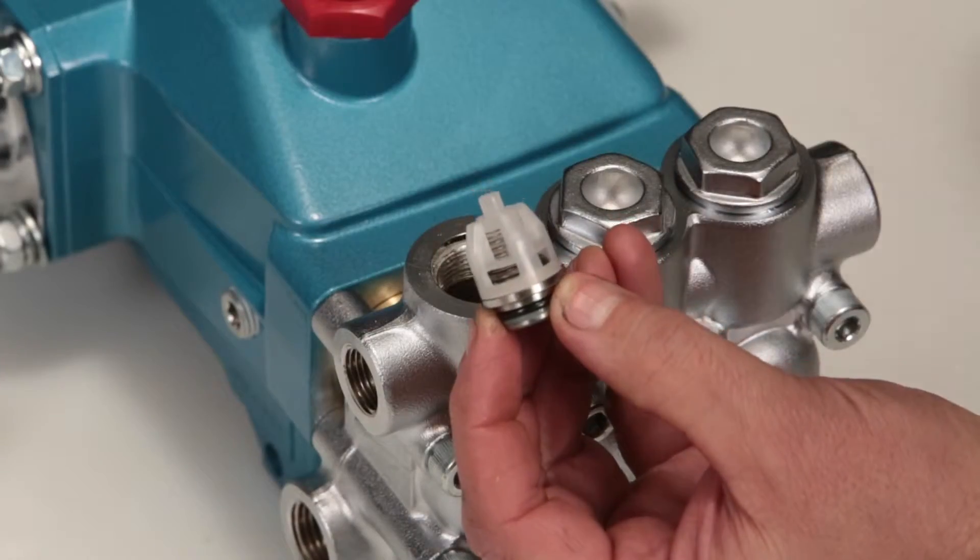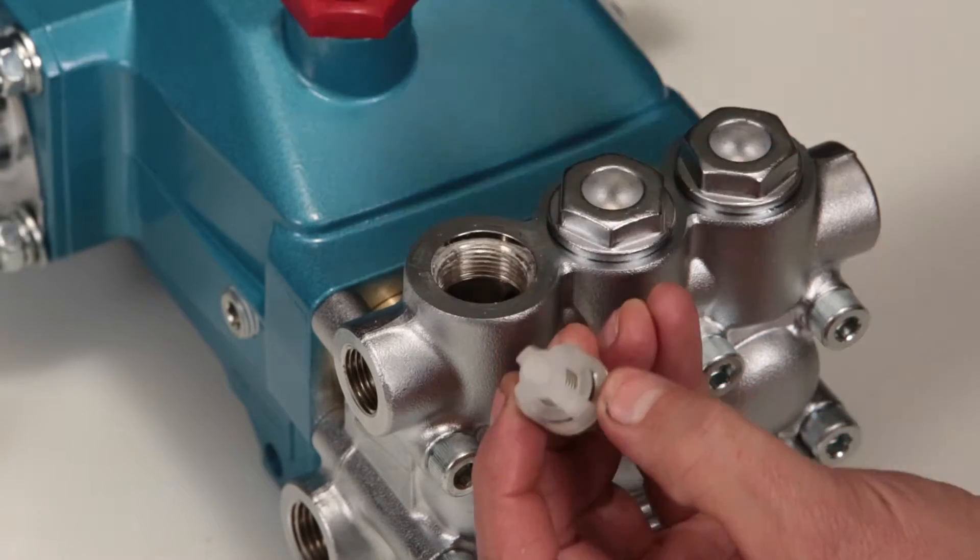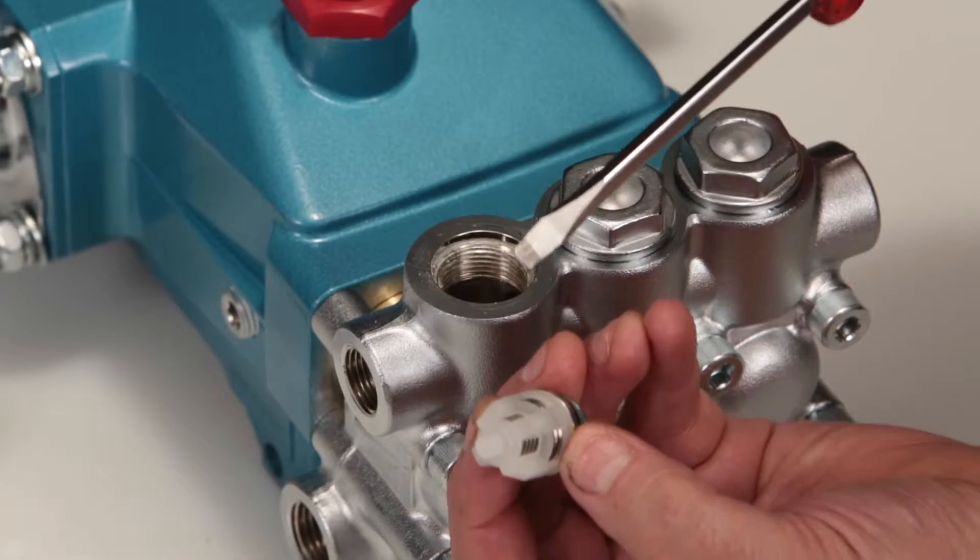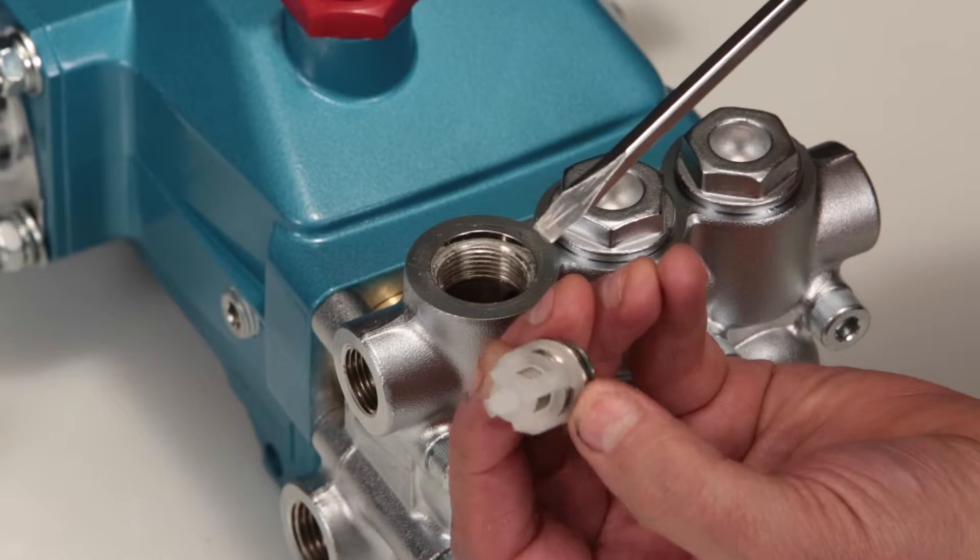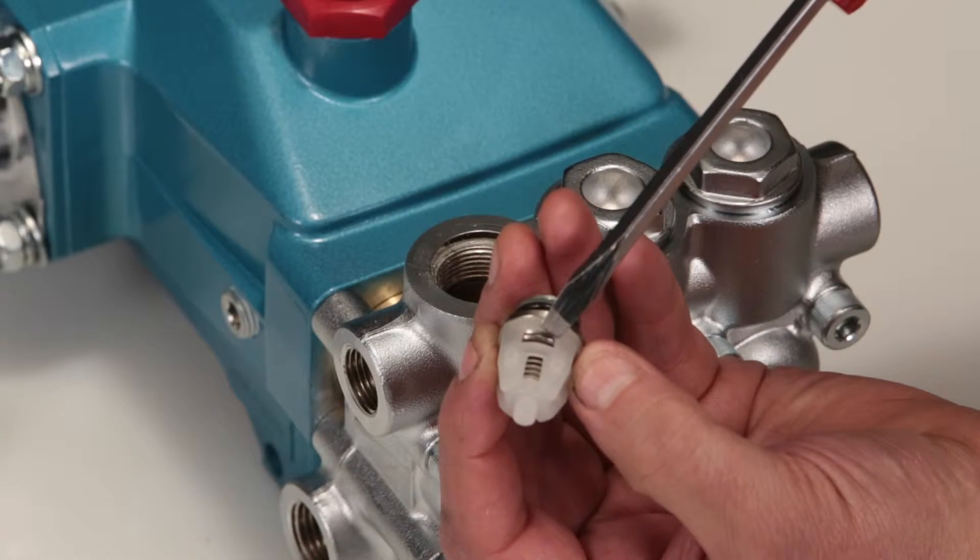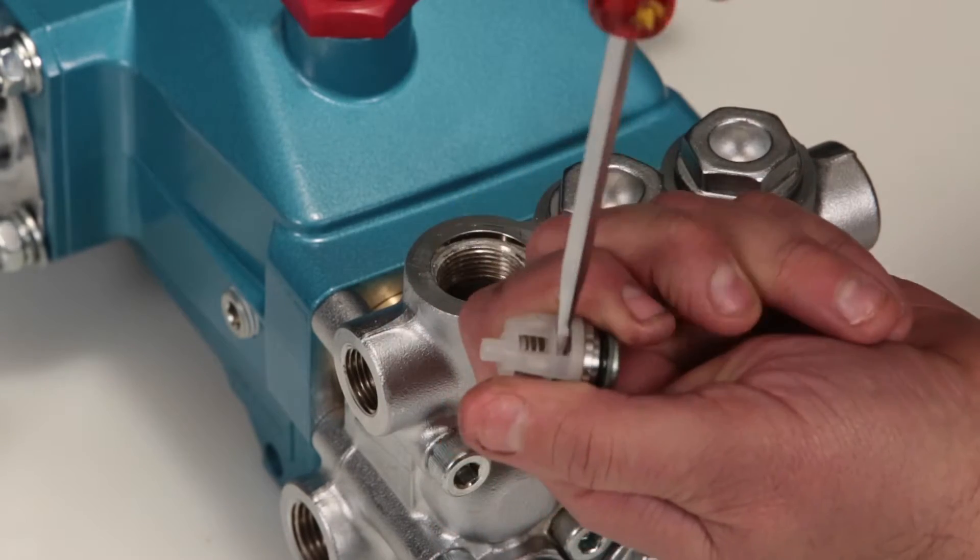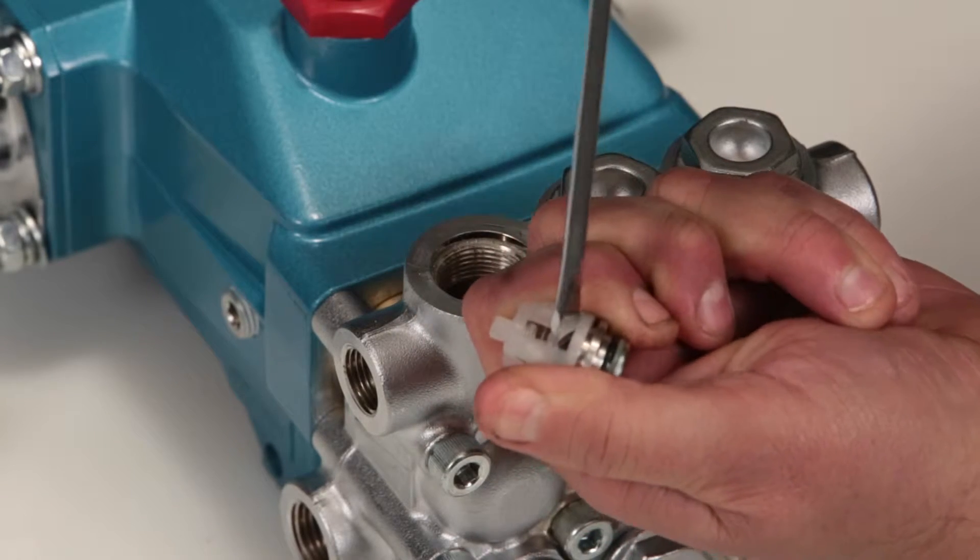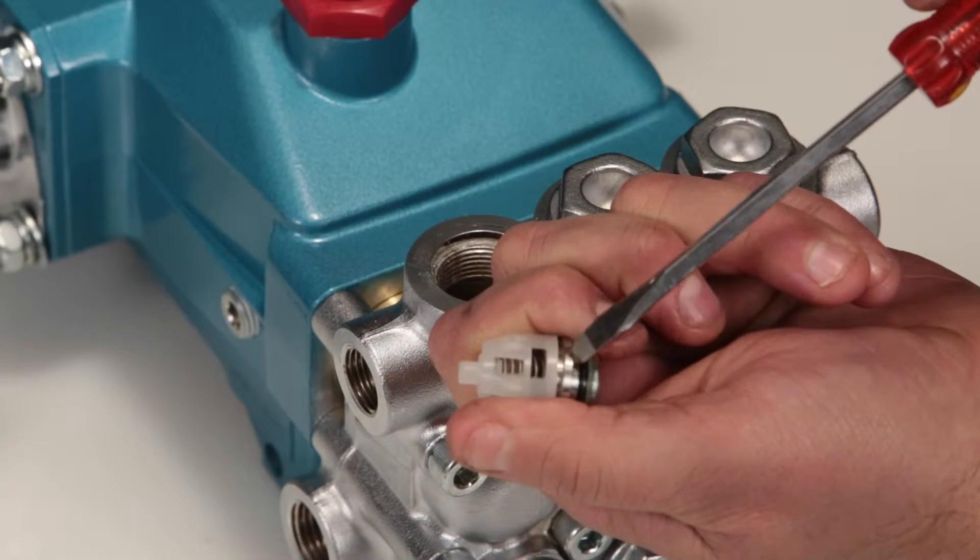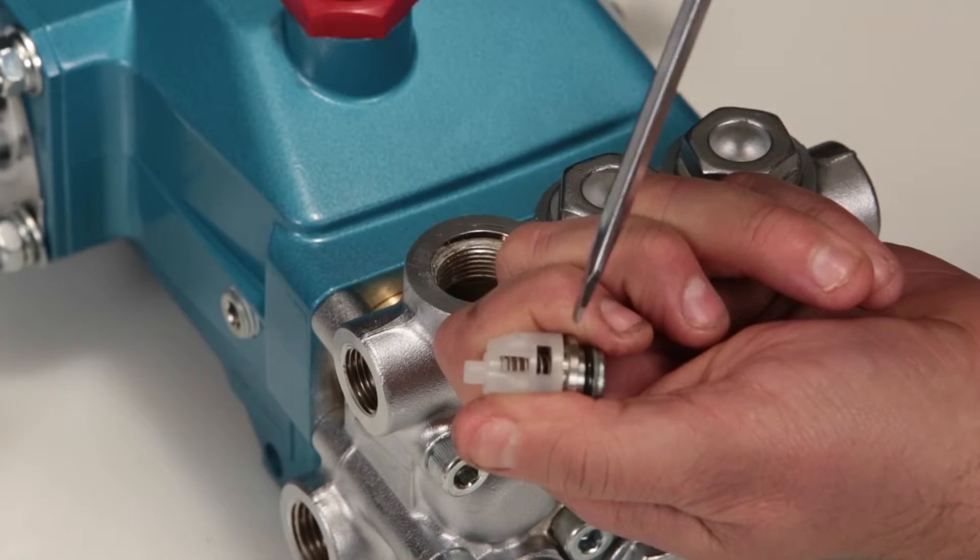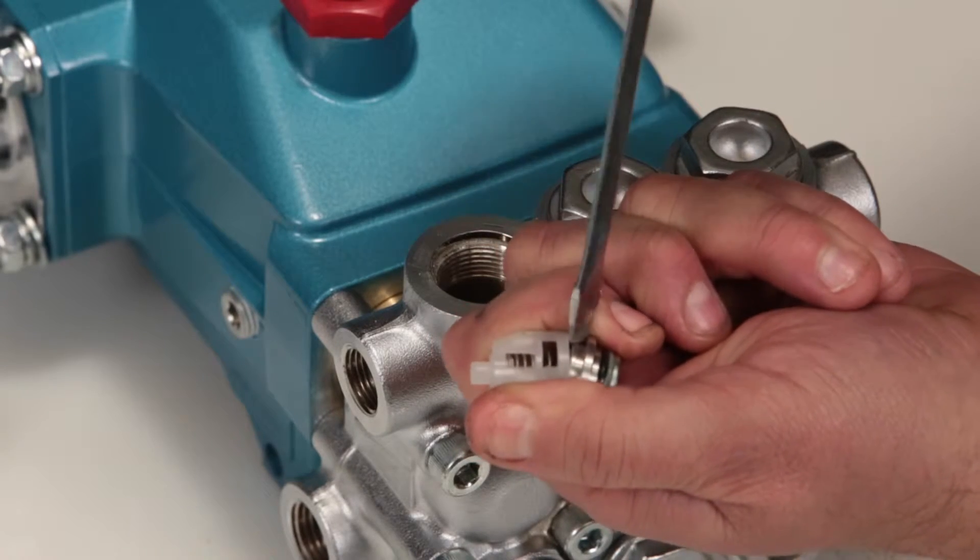If the valves are going to be reused, serviced, or inspected, the assembly can be dismantled. Start by inserting a flat-tip screwdriver through the spring retainer just above the valve and twist to create a small gap between the valve retainer and valve seat. Place flat-tip screwdriver in the gap and twist to completely separate.